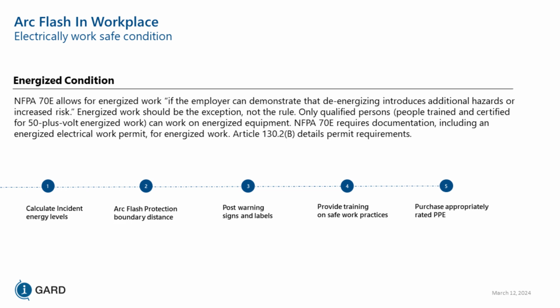You can work live, but the employer has to demonstrate that de-energizing causes more of a hazard than working on it live. So you have to calculate the risk of having an arc flash. This is why the subject is the risk, minimizing the risk, not the arc flash hazard itself. The arc flash hazard is the arc flash hazard, but we're trying to minimize the risk of having an arc flash hazard. So you have to make sure that the people are trained and certified.